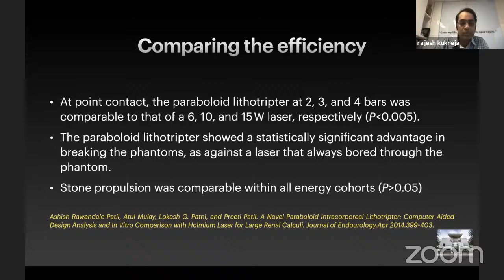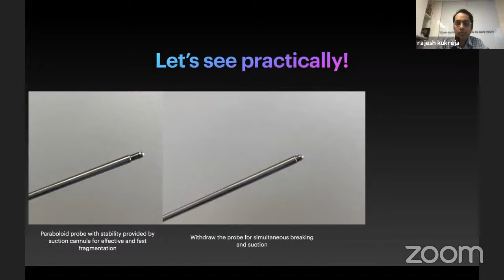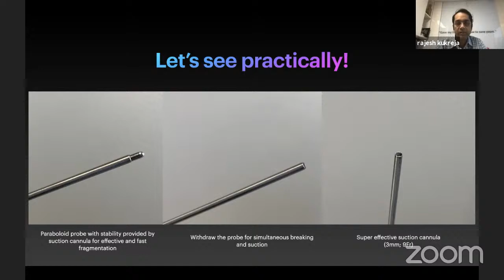So let's see practically. This is our own Indian lithoclast. I'm telling you, this is the one I am using, the Nidhi lithoclast. You have a parabolic probe, stably provided with a suction cannula for effective and fast fragmentation. There you can withdraw the probe for simultaneous breaking and suction. So you can set it as per your need. And then once you're through, you can use it as a very effective suction cannula. That is a 3 mm, 9 French suction cannula.